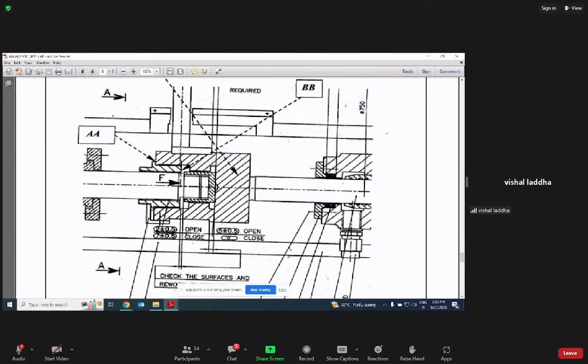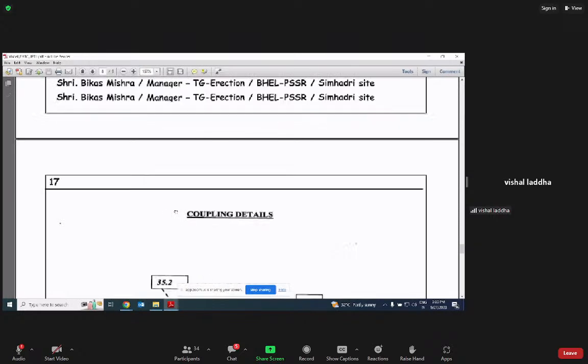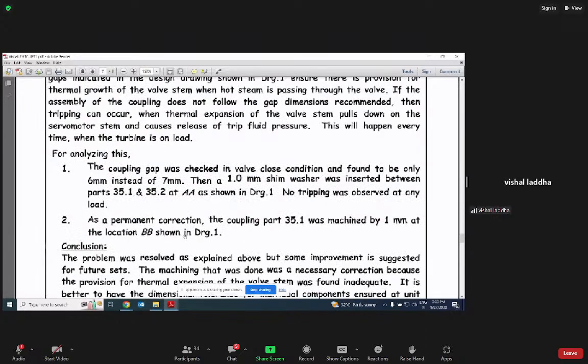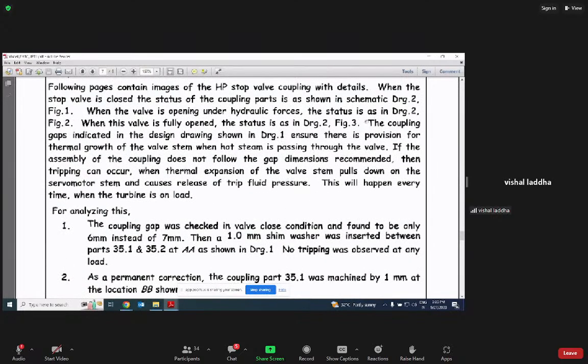Here is the gap. You check the arrow mark. Extra material growth was found in this area. The coupling gaps indicated in the design drawing ensure there is a provision for thermal growth of the valve stem when hot steam is passing through the valve. If the assembly of the coupling does not follow the gap dimensions, then tripping can occur when thermal expansion of the valve stem pulls down on the servo motor stem and causes release of trip fluid pressure.